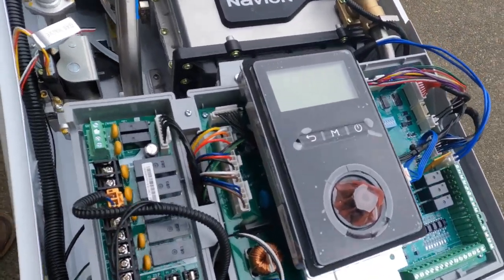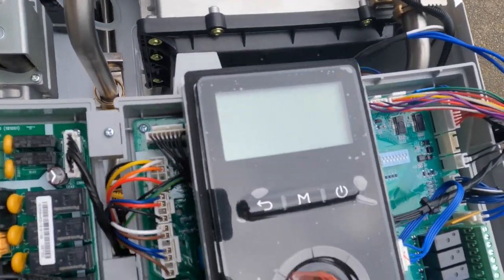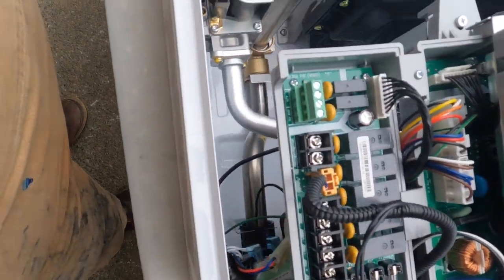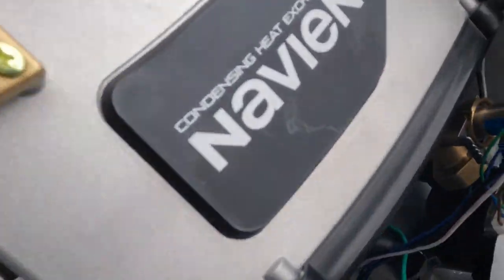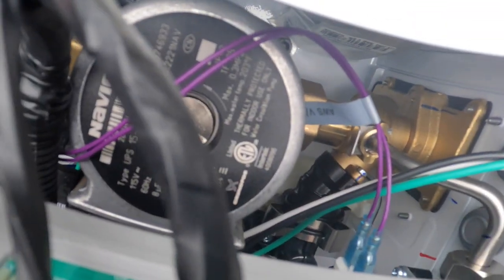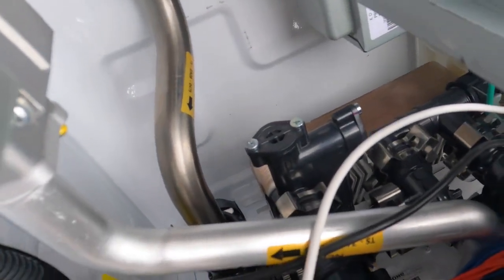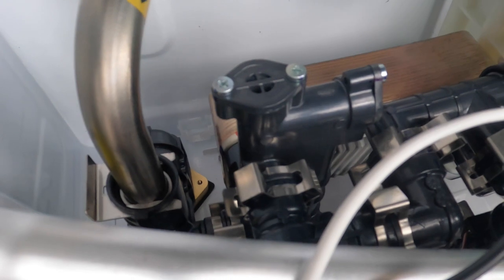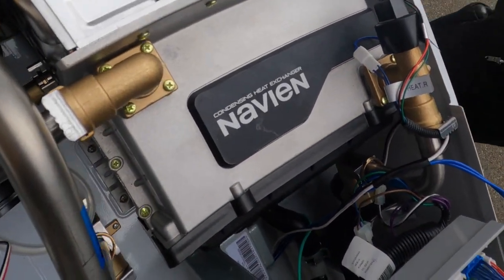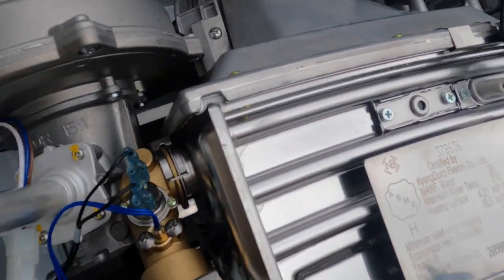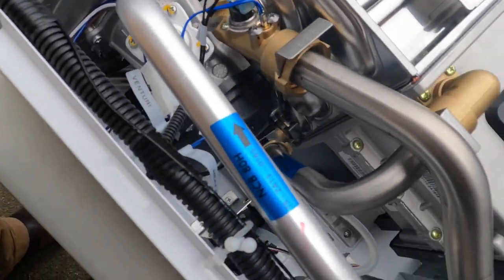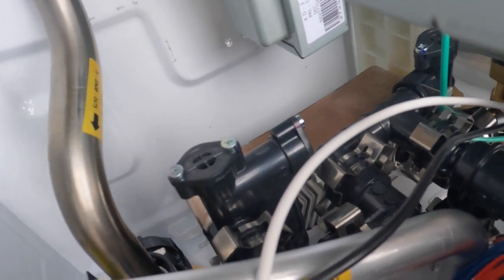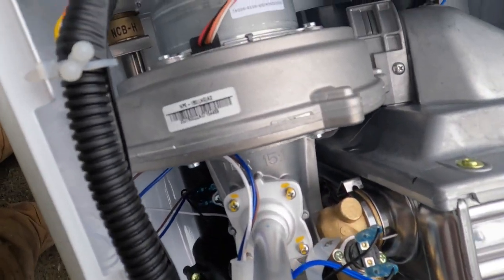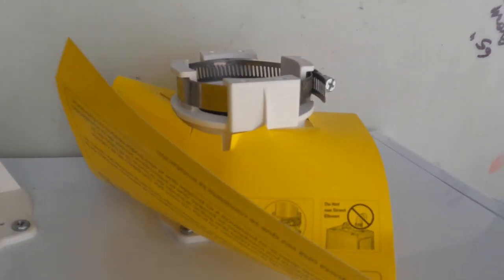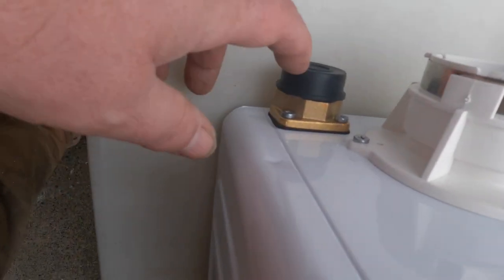This is the inside look at the Navien Combi Boiler. Here's our control board, our interface panel, some fusing and relays over here, main power switch there. Down inside you can see the circulator pump there for the heating loop, for the primary loop, and then down in there you can see the plate frame heat exchanger, and this is the main combustion area slash heat exchanger that heats the water. The little plate frame heat exchanger is for the domestic hot water. Here we have the inducer fan, the outside air intake, and the exhaust outlet. Over here will be an automatic air vent to let air out of the system.